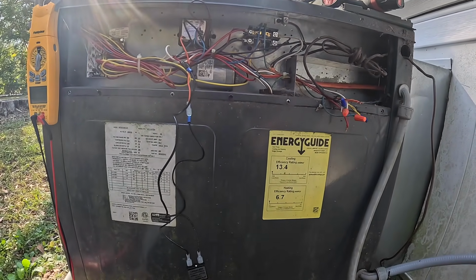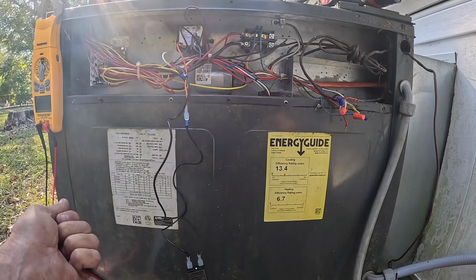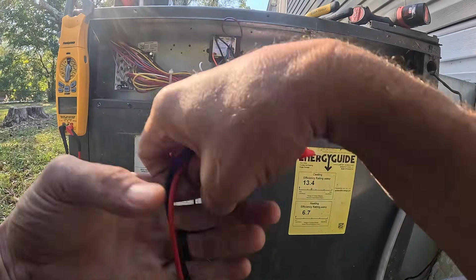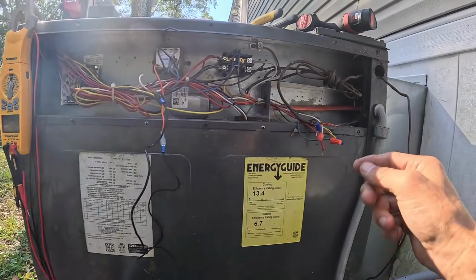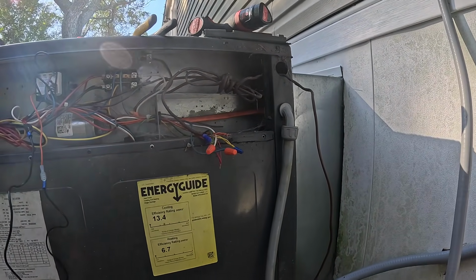All right, we need to look at our reversing valve and wires and coils and check on it, because the reversing valve wire is what's popping the fuse.